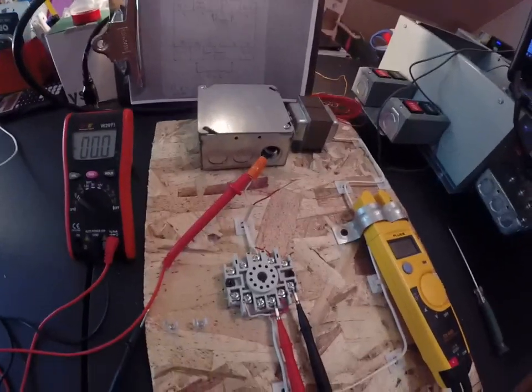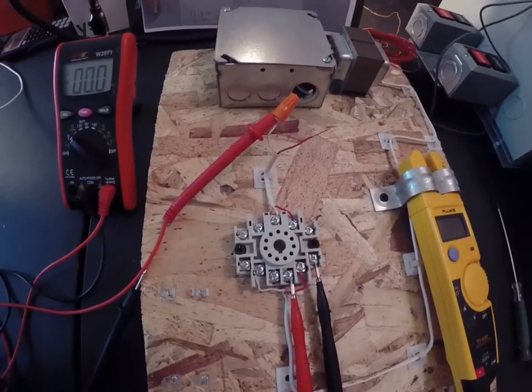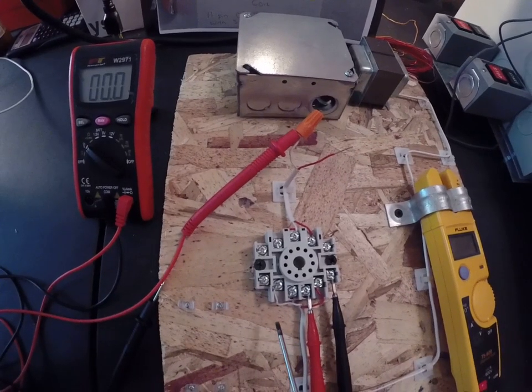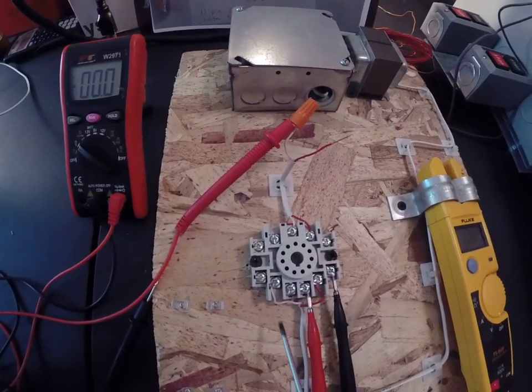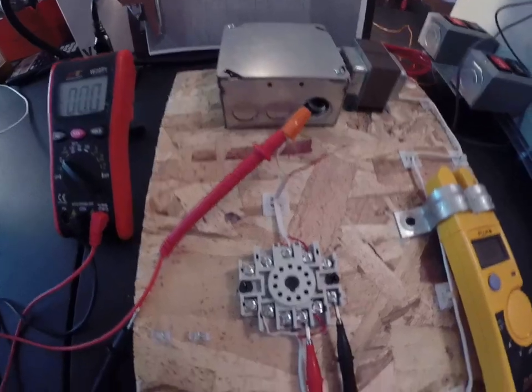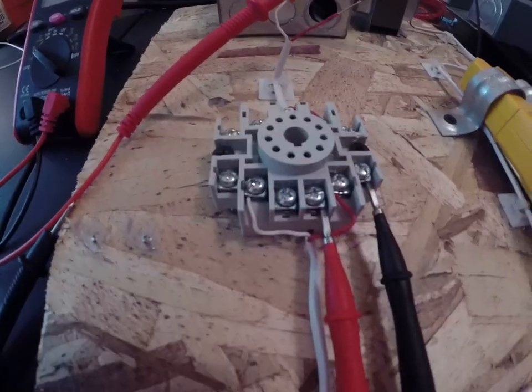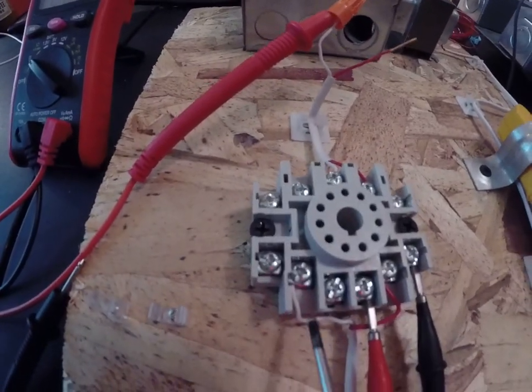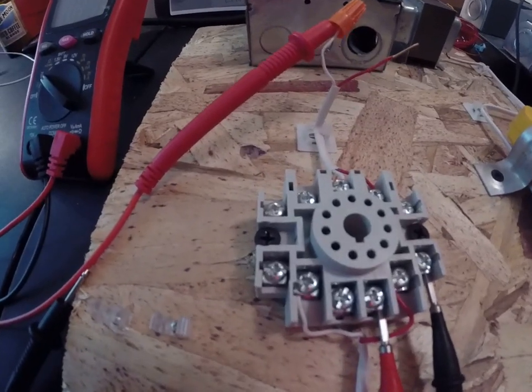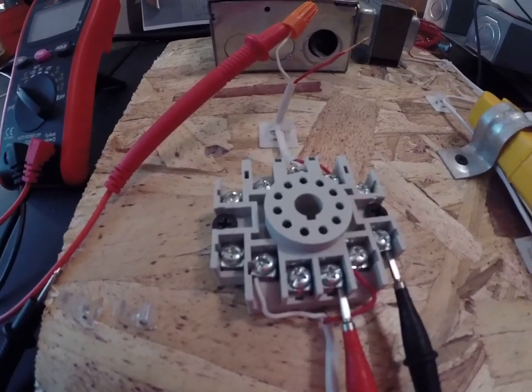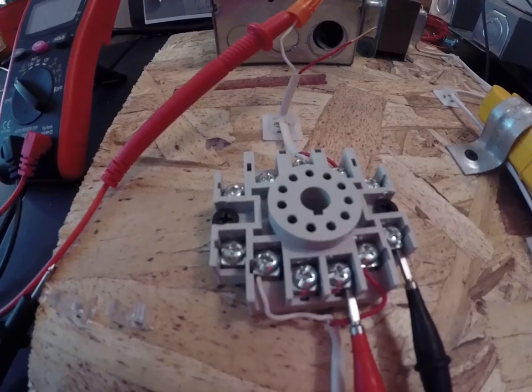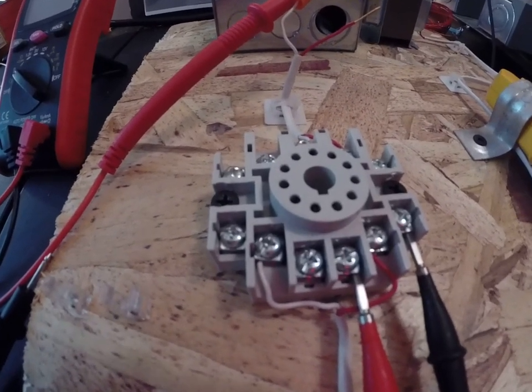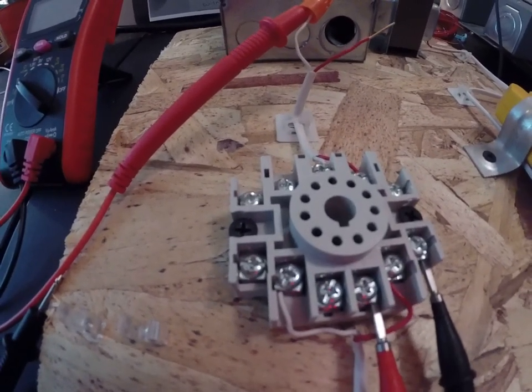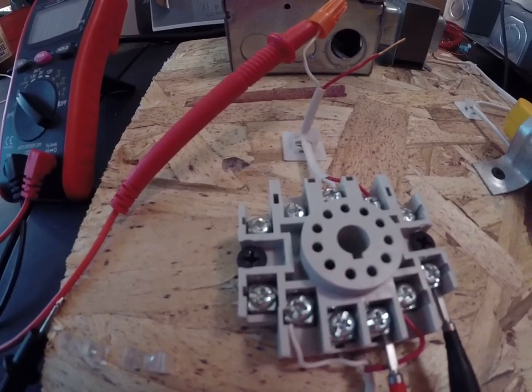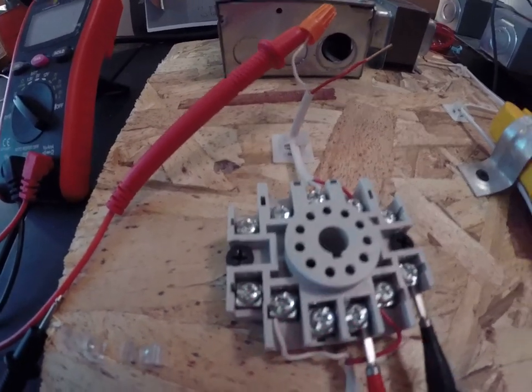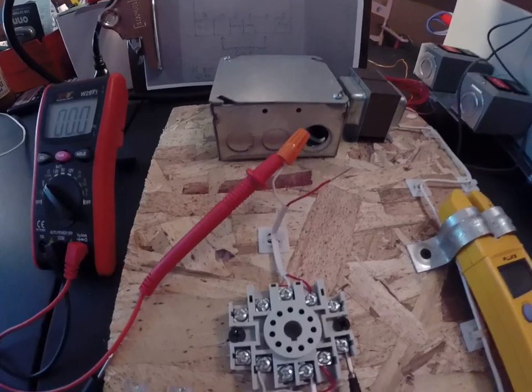You might remember, or if you haven't done the homework yet, the way these work is coil voltage has to be present at all times. So all I'm doing here is putting voltage on this white and red wire to the coil, and that's how those have to be. The reason there has to be power to the coil at all times is because that's what generates the DC voltage on the trigger switch, and we need the trigger switch in order for the relay to actually work.